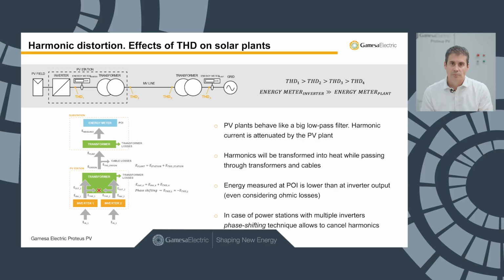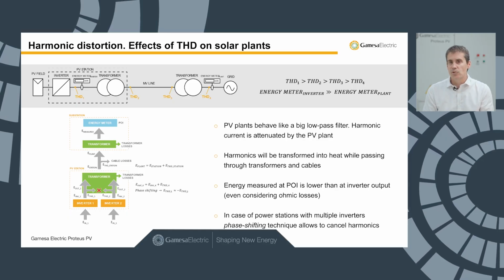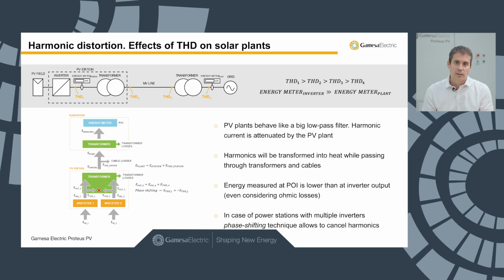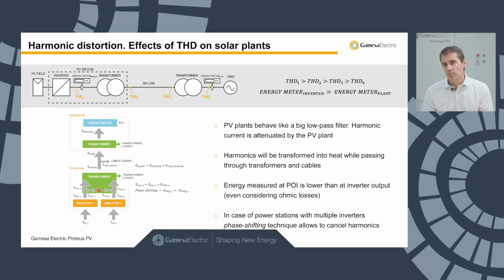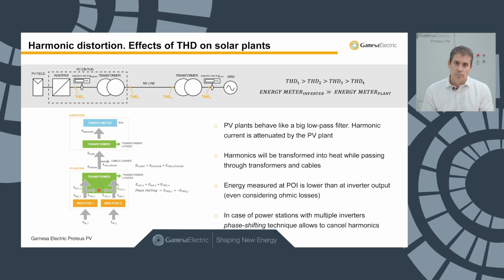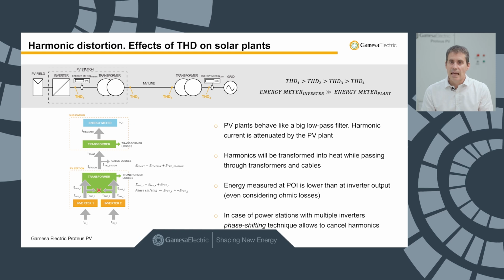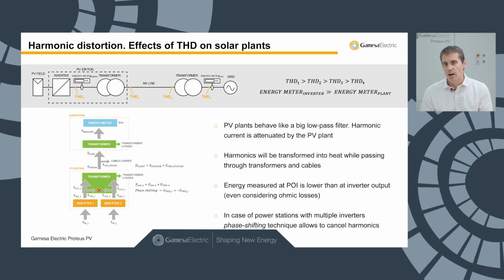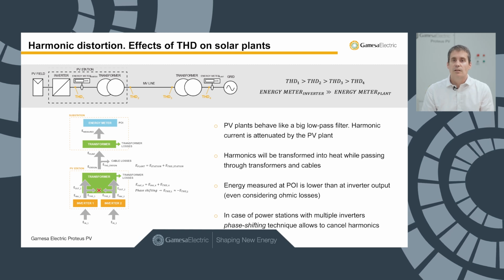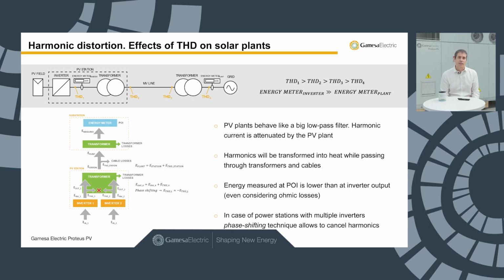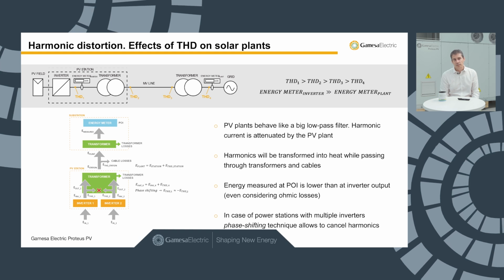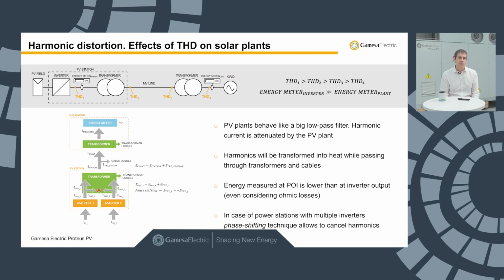Well, now let's talk about the effects of harmonic distortion in terms of produced energy, and then we will introduce how the harmonics are mitigated. Basically, the harmonics produce heat in the transformers. Moreover, they heat the cables and every ohmic load. So we expect less energy produced at the point of interconnection than the energy produced by the inverters. On the other hand, we have to notice that plants mitigate the harmonics because they are big low-pass filters, and so the harmonic current is attenuated by the PV plant.